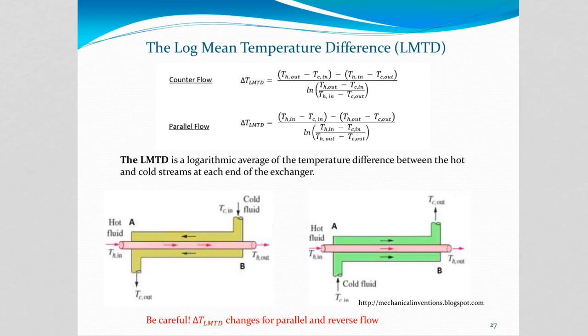Another extremely important concept, formula to calculate heat exchange, heat transfer, is using the log mean temperature difference, or LMTD. The LMTD is the driving force for the heat exchange between the two fluids, and when the LMTD value increases, the amount of heat transfer between the two fluids also increases. And LMTD is used for calculating the heat duty of the heat exchanger. And these are the formulas.